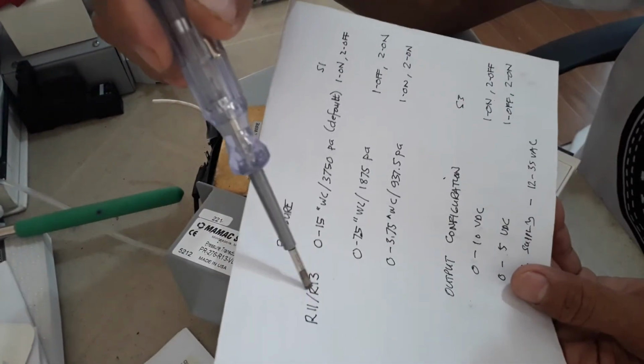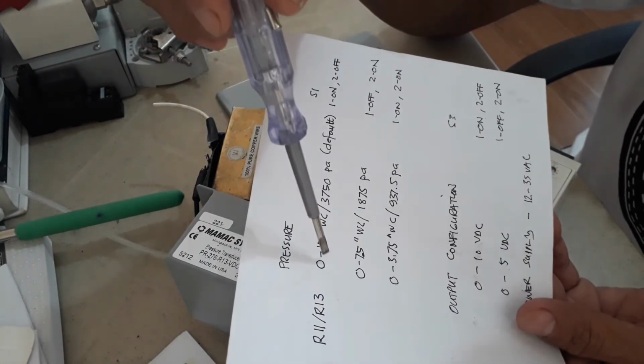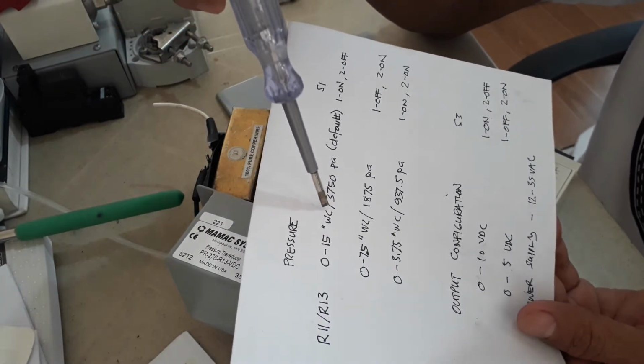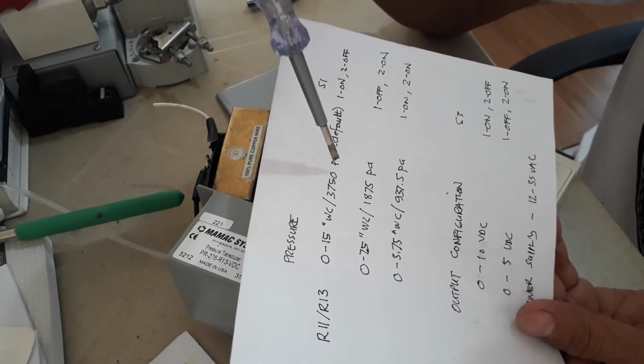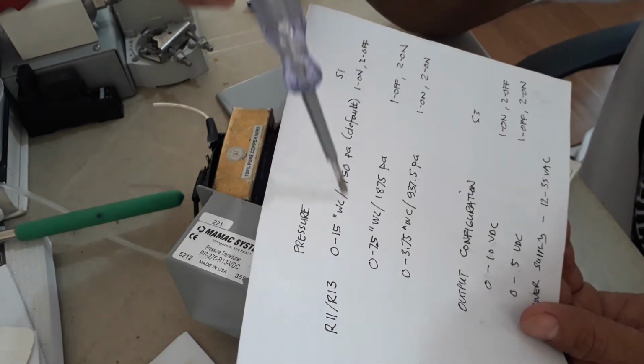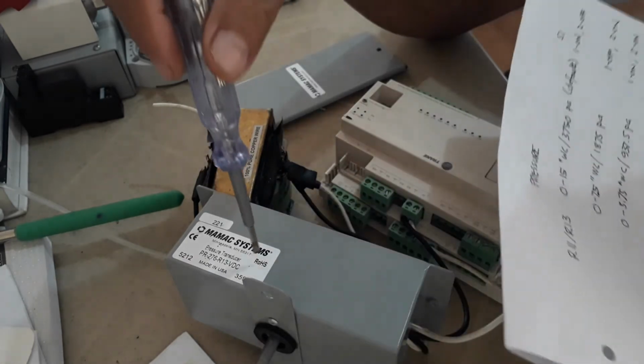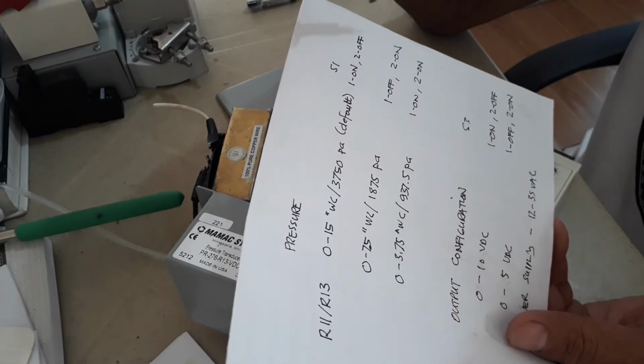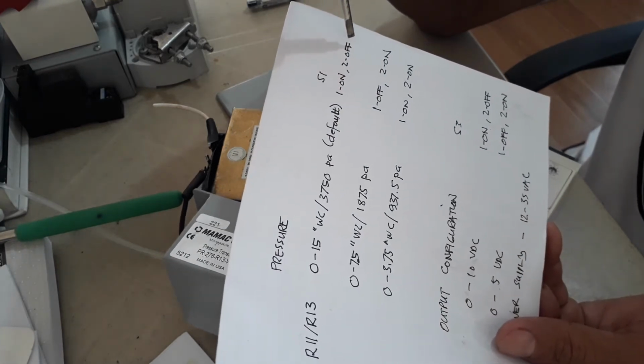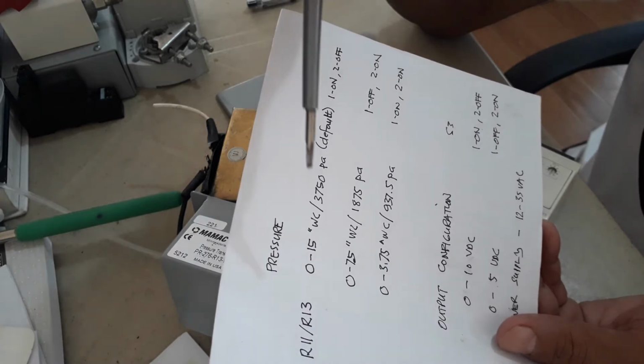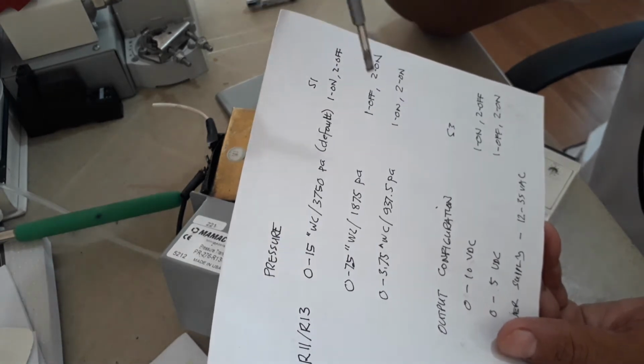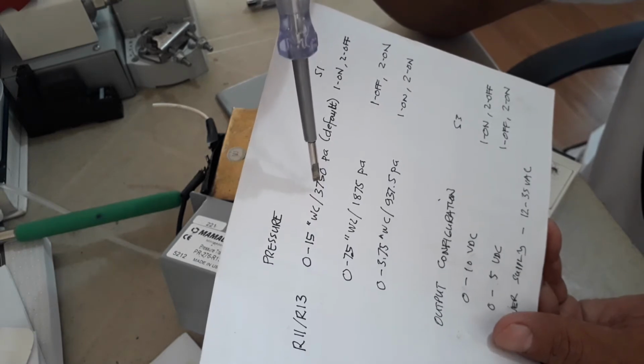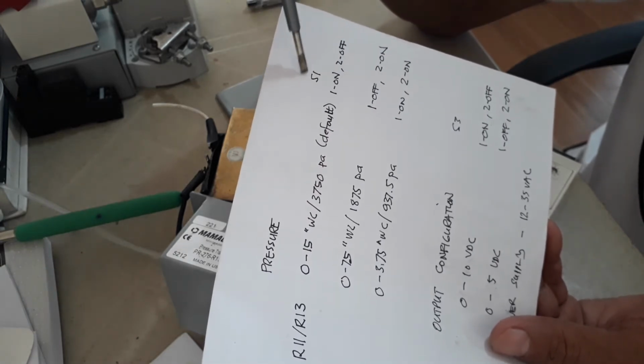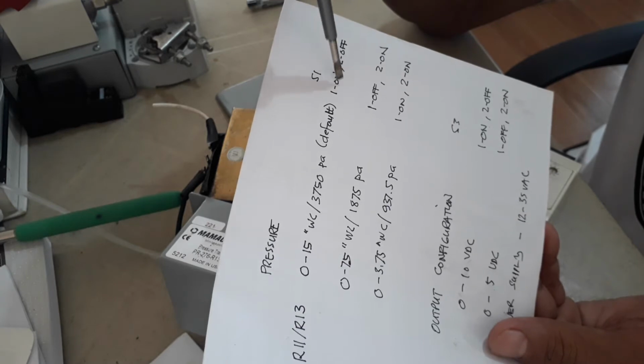Now the pressure range is, since this is R13, 0 to 15-inch water column or 3,750 Pascal. So this is the default pressure range of this duct pressure sensor or transducer. Now for the S1, 1 is on and 2 is off. Okay? So if you are going to set it to 0 to 3,700 Pascal, so this is the switch 1 configuration. 1 is on, then 2 is off.